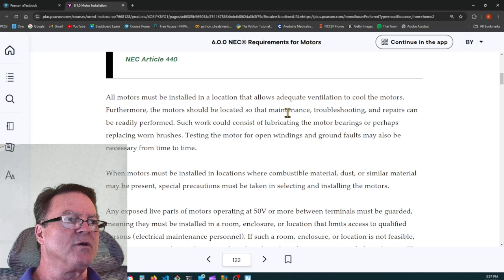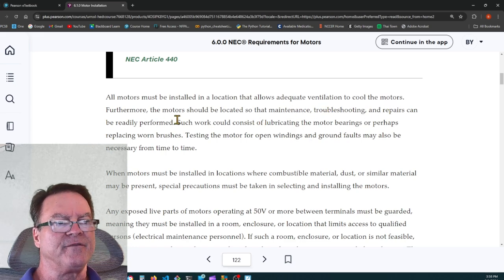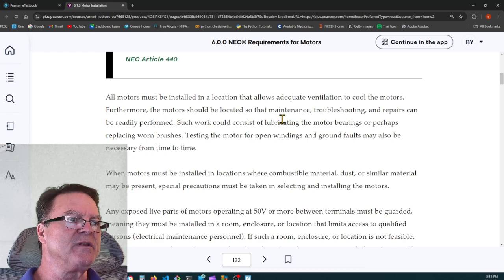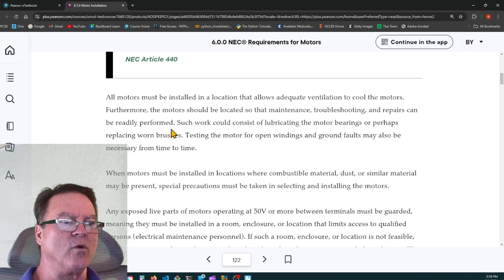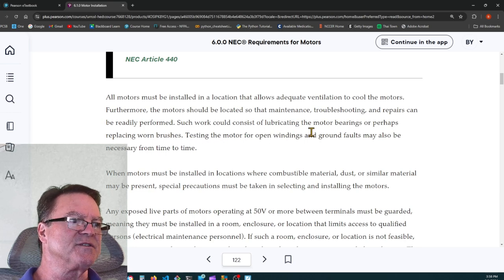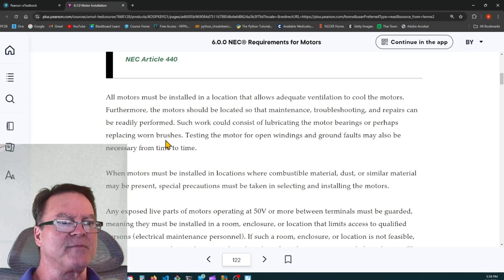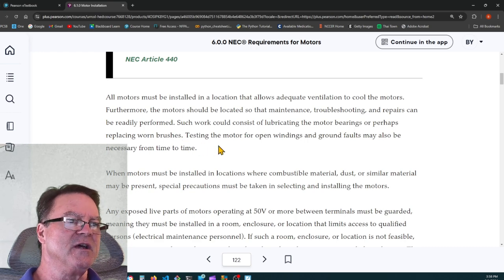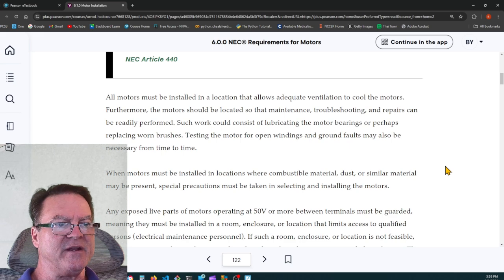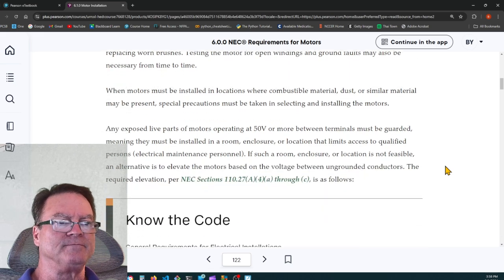All motors must be installed in a location that allows adequate ventilation to cool the motor. Further, the motors should be located so that maintenance, troubleshooting, and repairs can be readily performed. Such work consists of lubricating the motor bearings or perhaps replacing worn brushes. Testing the motor for open windings and ground faults may also be necessary from time to time.